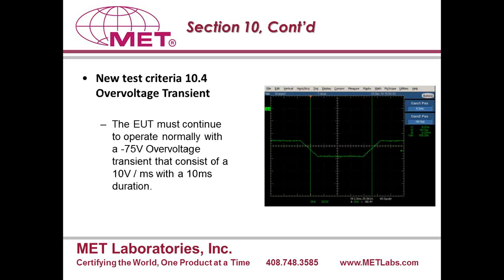The next change is documented as Section 10.4, over voltage transient. This is not necessarily a new requirement in the industry. This requirement has always been there as part of the AT&T requirements for DC systems, as part of the AT&T verification document. However, as an effort to harmonize the requirements, they have now added this requirement to GR-1089 Section 10. Basically, the idea is that the device has to operate at minus 48 volts. Then, with the slope of 10 volts per millisecond, it goes to minus 75 volts. It stays at minus 75 volts for 10 milliseconds, and then following the same slope of 10 volts per millisecond, it goes back to minus 48 volts. And during this time, the device has to continue to operate.